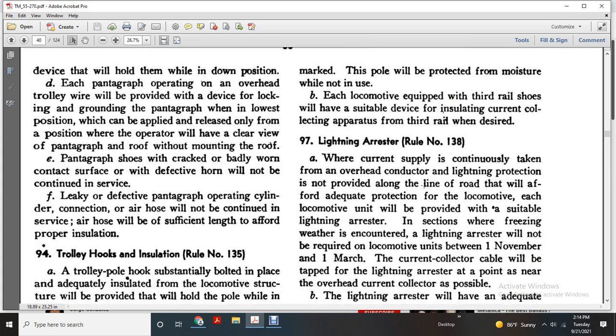97, the lightning arrester, rule number 138. The current supply continually taken from the overhead conductor, lightning protection not provided along the line of road that will afford adequate protection for the locomotive. Each of the locomotives of the unit will be provided with a suitable lightning arrestor. In sections with freezing weather, the lightning arrestor will not be required on locomotives between November 1st and March 1st.